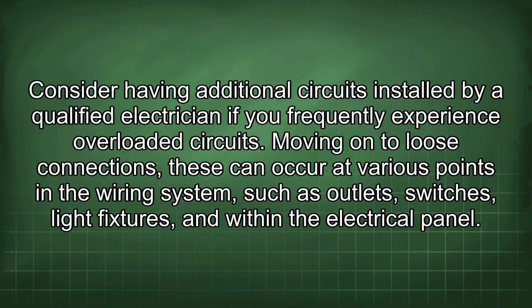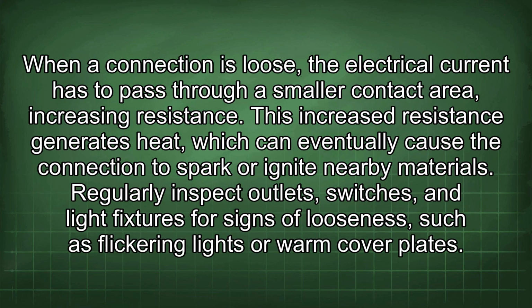Moving on to loose connections, these can occur at various points in the wiring system, such as outlets, switches, light fixtures, and within the electrical panel. When a connection is loose, the electrical current has to pass through a smaller contact area, increasing resistance. This increased resistance generates heat, which can eventually cause the connection to spark or ignite nearby materials.